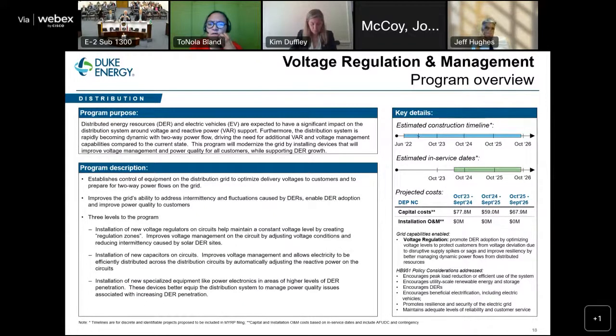Power electronics can damp out those rapid changes, while regulators and capacitors perform the more traditional function of adjusting as load moves up and down during the day. Think of capacitors and regulators as the coarse voltage and reactive power adjustments, and the power electronics as giving you fine, instantaneous adjustment to deal with those fluctuations.